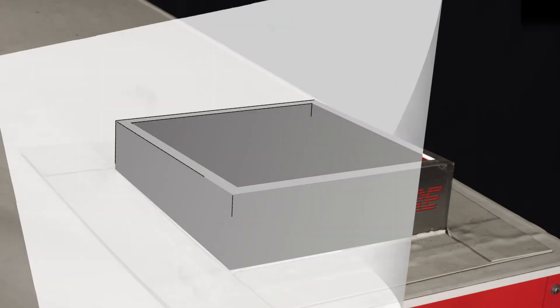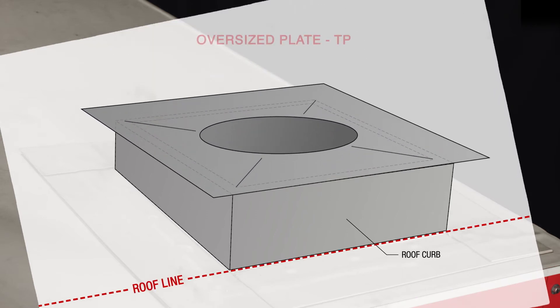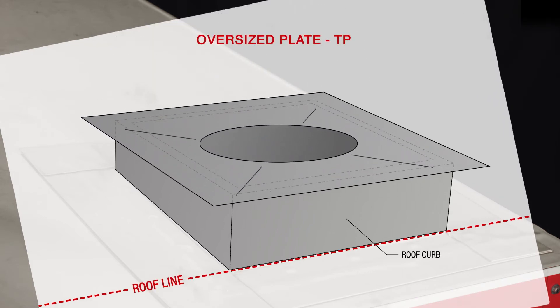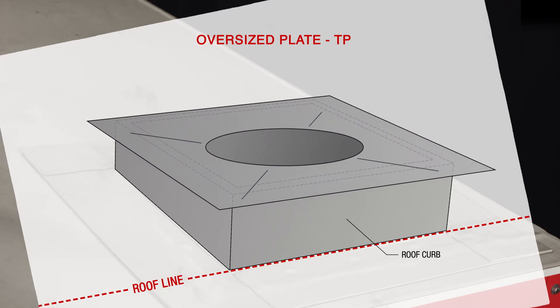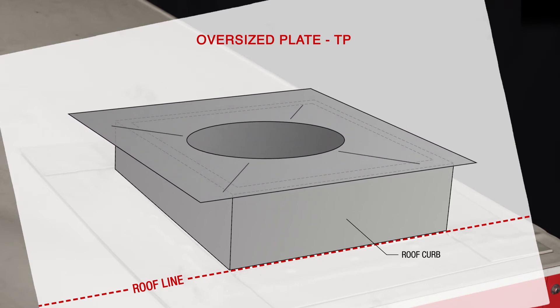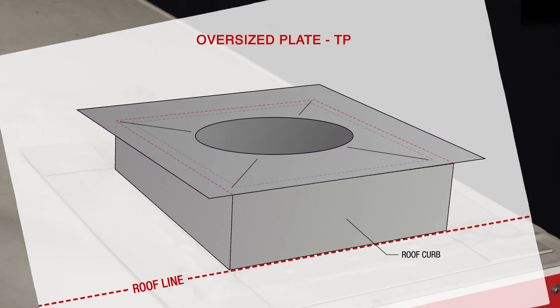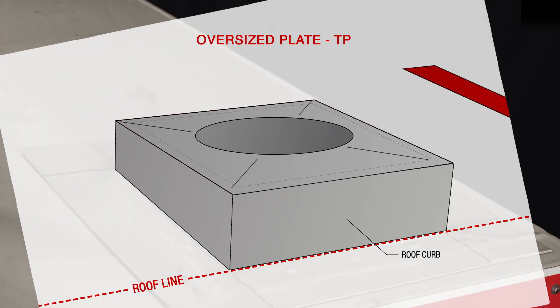To install an oversized TP plate, first place it on the curb. The plate can be positioned off-center with the curb, provided that the minimum clearance to combustibles is maintained. Once in place, you must trim off the excess plate material to allow for fan placement.